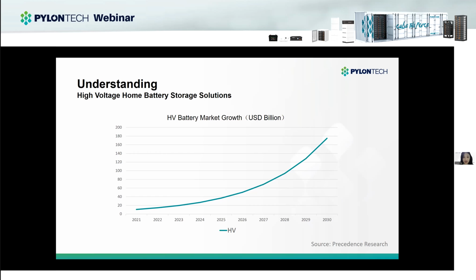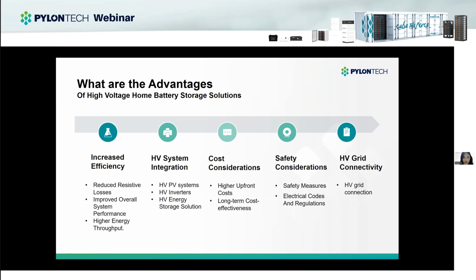Sometimes it could extend to 200 amps. The customer should use thicker power cables, and the heat would also become larger. If you use a high voltage battery, the current is small and the interference in the system is small. Then the efficiency of the high voltage PV storage system is higher. So the first advantage of the high voltage ESS is increased efficiency. It will reduce the resistive losses during energy conversion and improve the overall system performance.